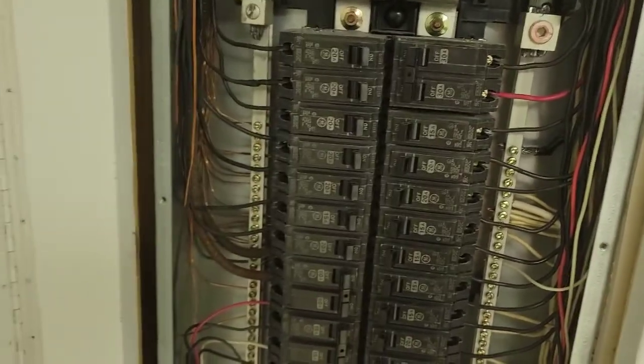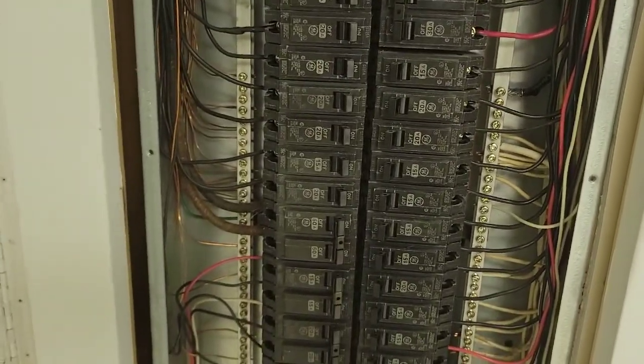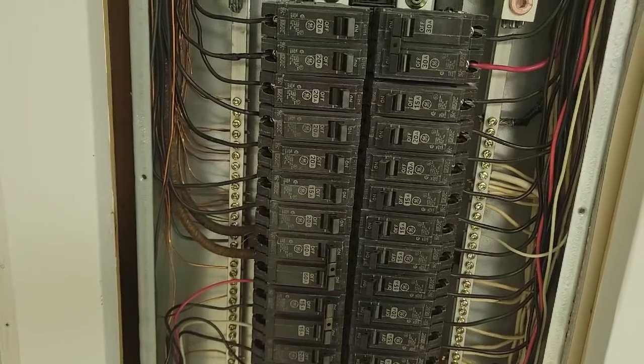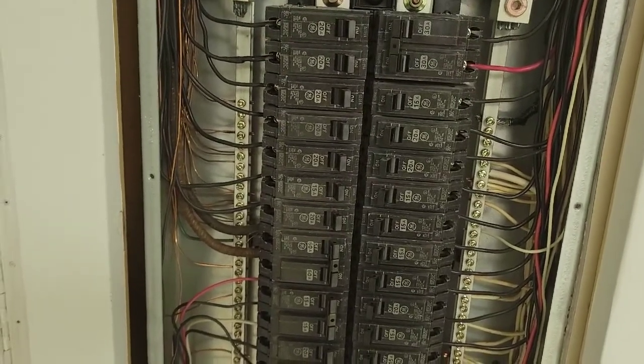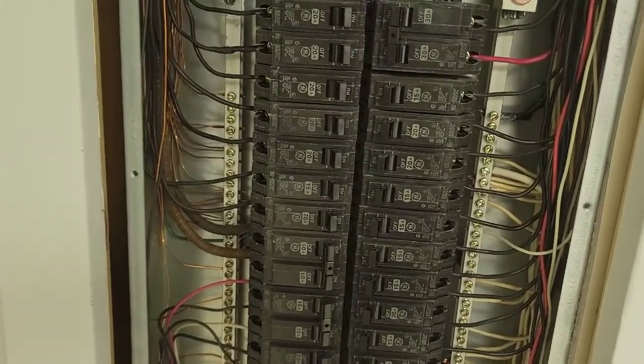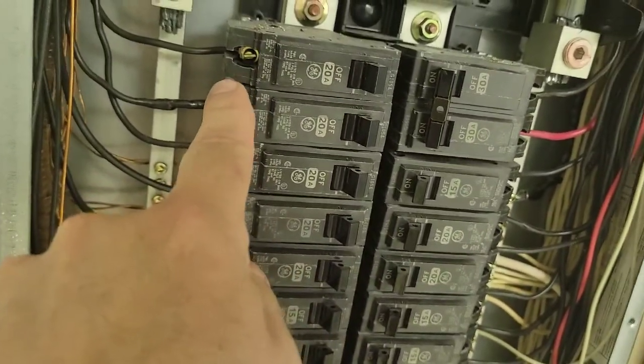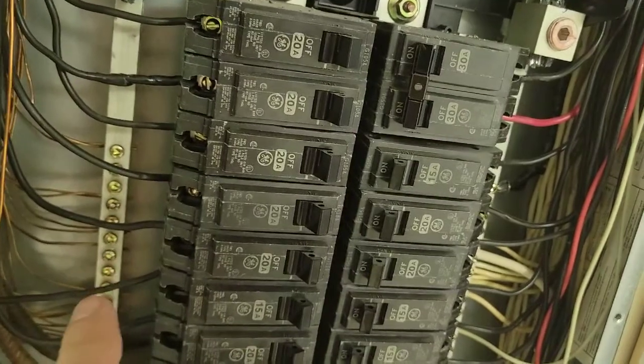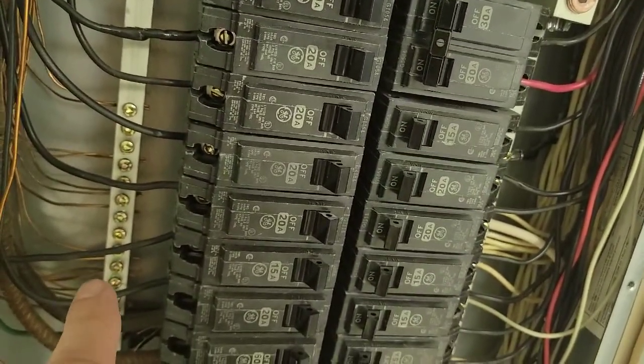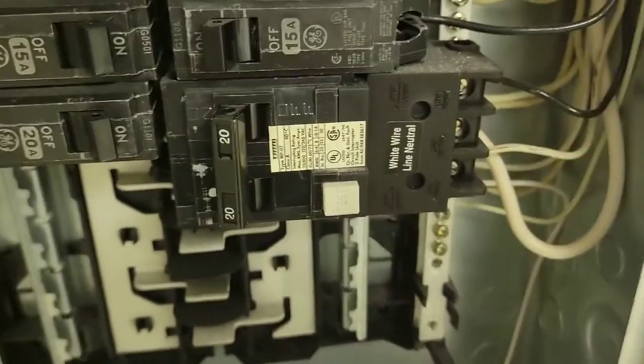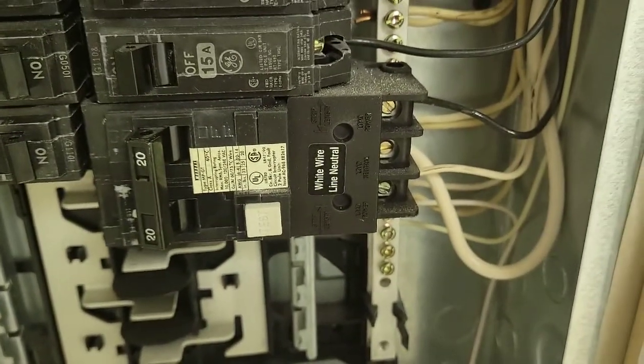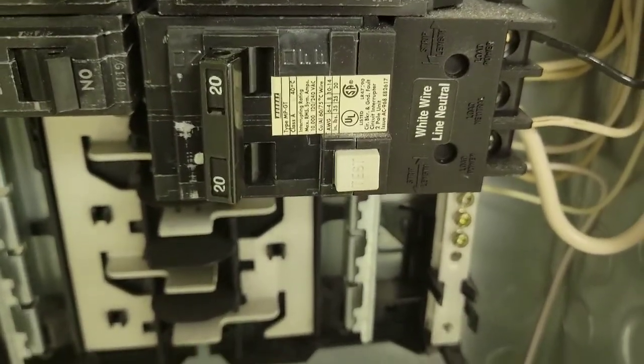So when we realized we had a source issue upstairs and we sorted out the lighting circuit independently fed by the 115 volt receptacle, I said, well, let's go see if we have a bad breaker. So we took the red lead of the multimeter and the black lead to the ground strip, and each one of these checked out 120 volts. All the way down the row was fine. And then we got to this little bad boy down here, and we weren't getting any voltage. And then I realized it was tripped.